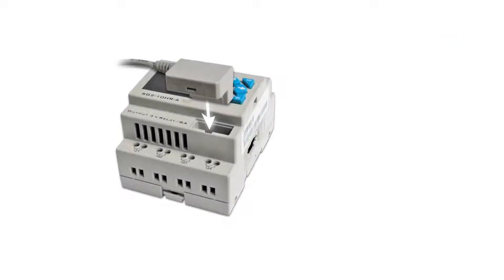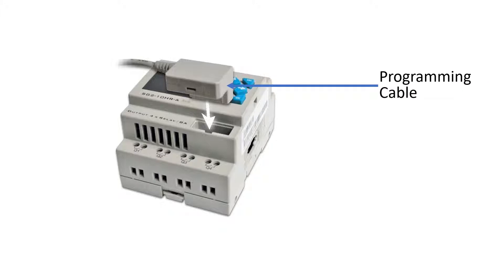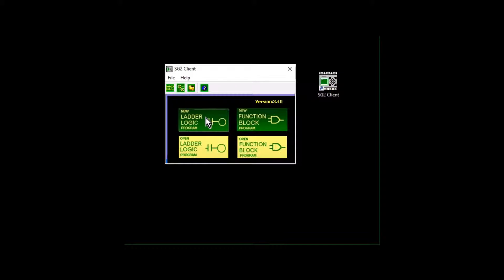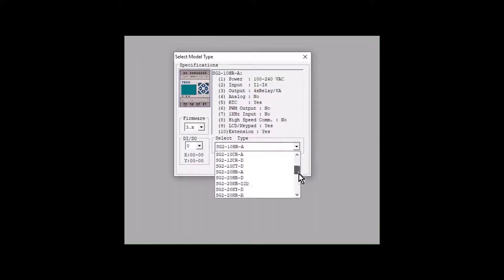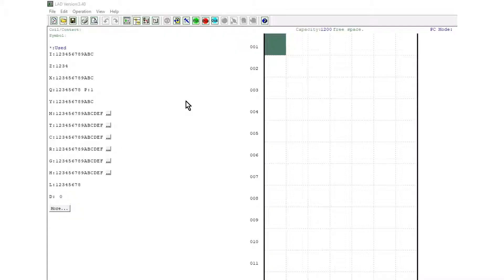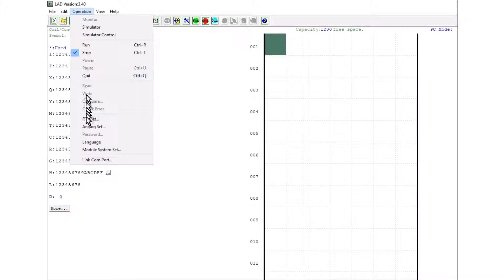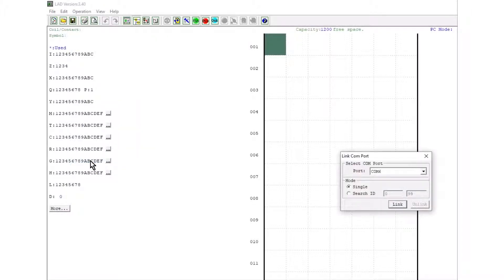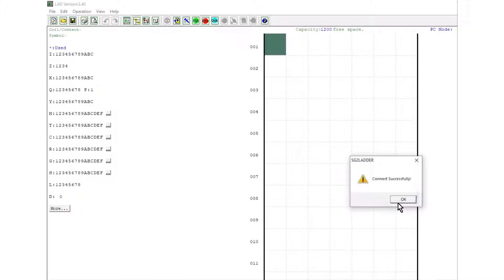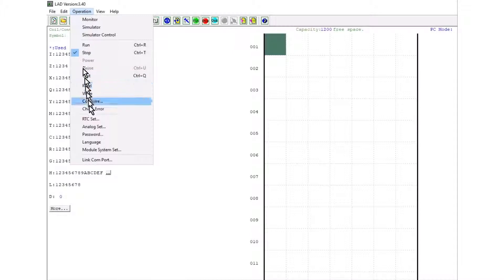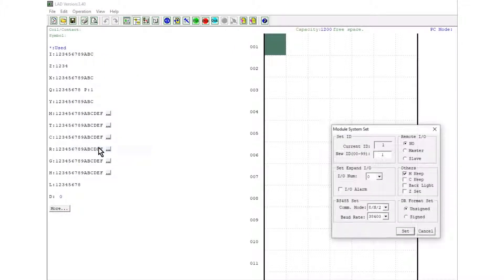The SG-2 will be set up to communicate on the RS-485 port with the client software. The RS-485 port is configured through the programming port. Open the SG-2 client software and select the SG-2 model. Select the PC's assigned COM port for linking to the SG-2 programming port, then click Link.